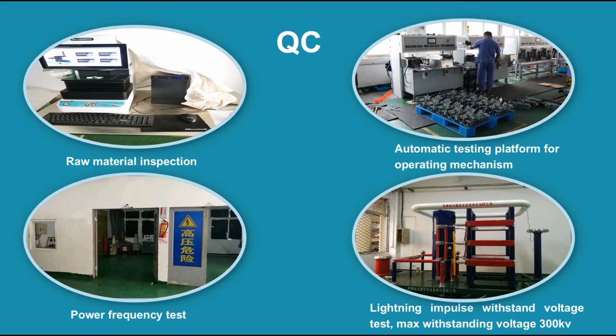The lightning impulse withstanding voltage equipment is usually only available in authority laboratories. According to the IEC standard, the lightning impulse withstanding voltage required for a 35 kV vacuum circuit breaker is 185 kV. But our equipment can test a maximum of 300 kV, which is much more than the IEC standard requires.